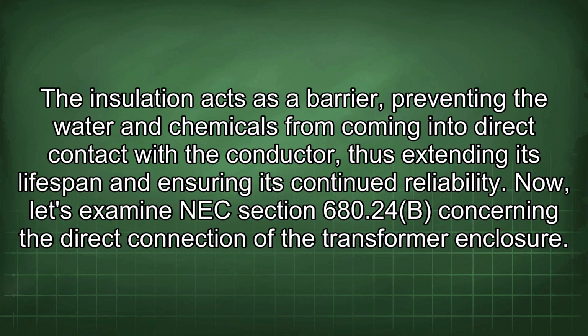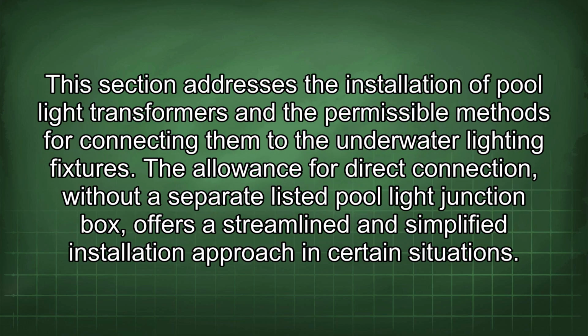Now, let's examine NEC Section 680.24(B) concerning the direct connection of the transformer enclosure. This section addresses the installation of pool light transformers and the permissible methods for connecting them to the underwater lighting fixtures. The allowance for direct connection, without the separate listed pool light junction box, offers a streamlined and simplified installation approach in certain situations.